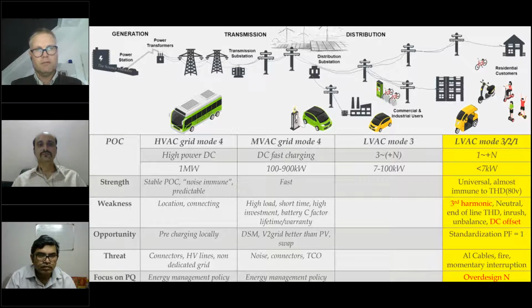It will multiply the power quality issue. So what's very important is the 3rd harmonic. That's the real weakness of the system, because you have 4 diodes, and you have a lot of 3rd harmonics, and that's giving a lot of extra current in the neutral. Also, when you have long lines, high impedance, long resistance, then at the end of the line the voltage will not look like a sinus anymore. In the old days, at the end of the line we could have a lower voltage, but with switch mode power supplies, it could also mean that at the end of the line you will have much too high voltages.